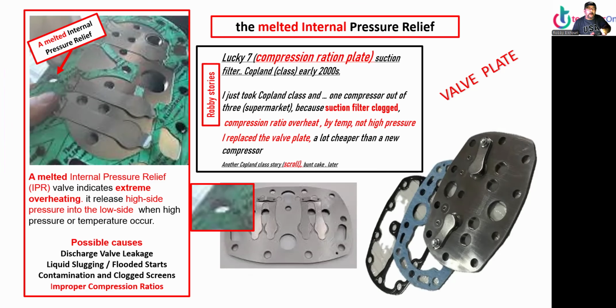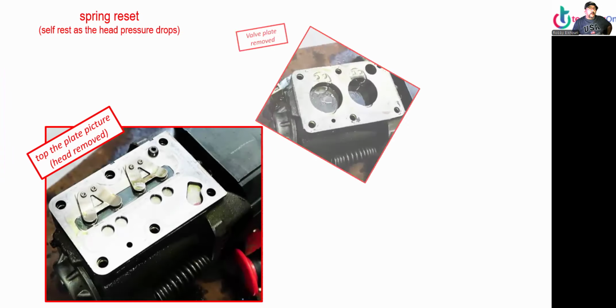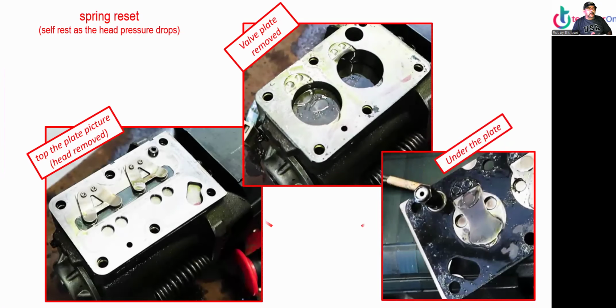All right, so spring, now we have the spring reset type. So the head plate you can replace. Isn't that cool? All right, now this is the top of the plate picture. This is the plate removed. This is under the plate. All right, and the spring automatic reset goes there, goes inside, and you can hear it. Psh, bypass from high to low when the compressor overheats.